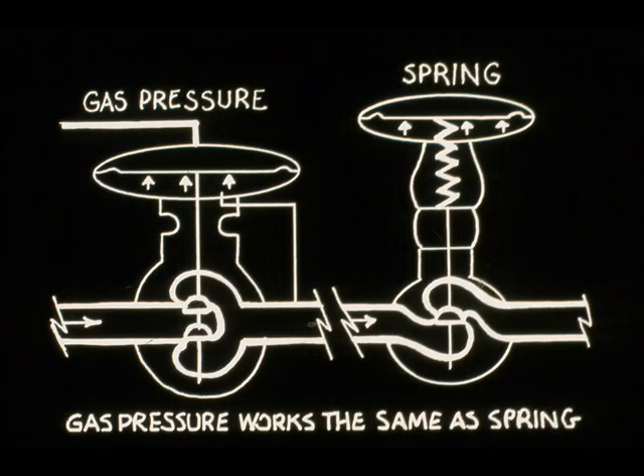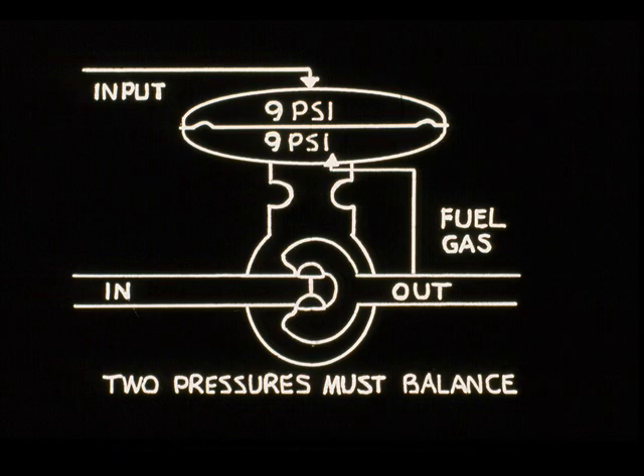The balance valve is used on low pressure gas applications. In this specific example, the downstream pressure of the fuel gas opposes the instrument signal. The instrument that signals the valve does not establish a direct valve position — it establishes an equal downstream pressure. Any downstream pressure variation that occurs will be sensed by the diaphragm, and the actuator will automatically reposition the valve to maintain the set downstream gas pressure.